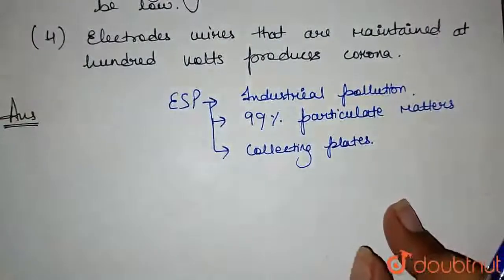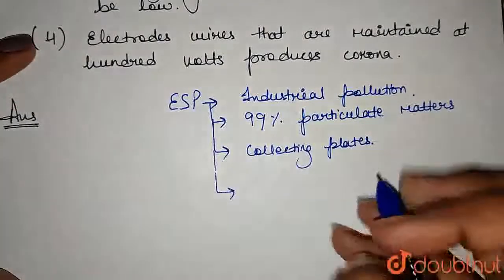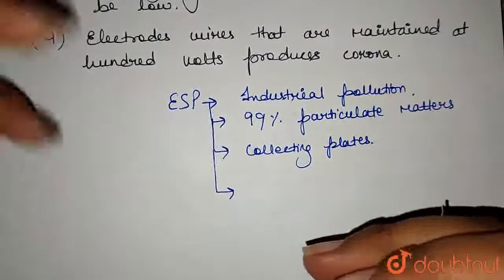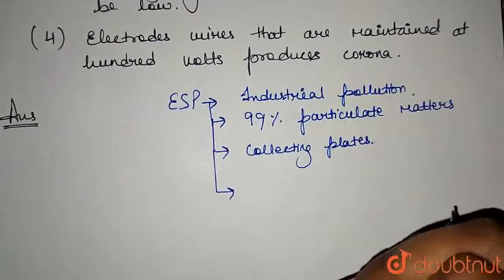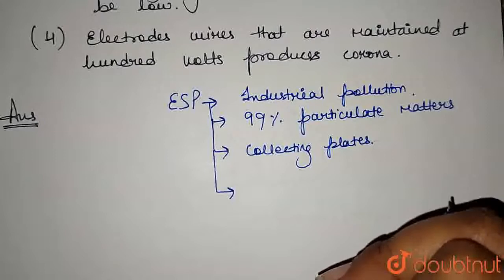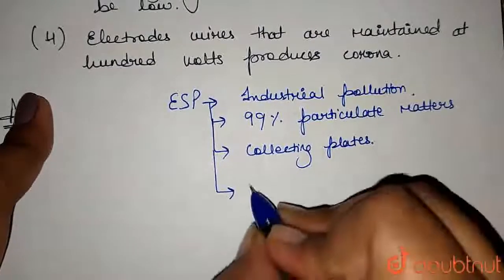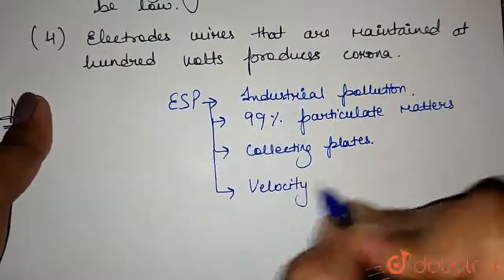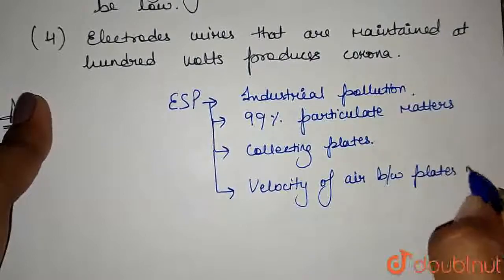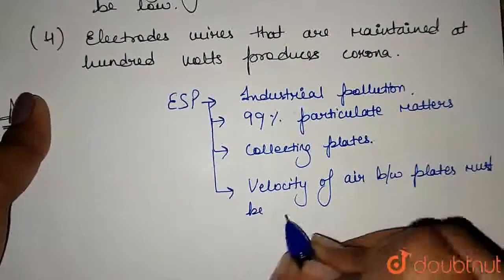The collecting plates are grounded — that is, they are connected to earth — so that the charged dust particles can fall off. The velocity of air between the plates must always be low so that the dust particles can easily fall off. If the velocity of air is too high, the dust particles will not fall and the process cannot continue.